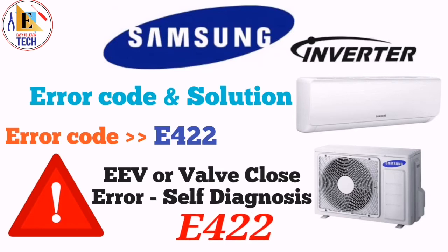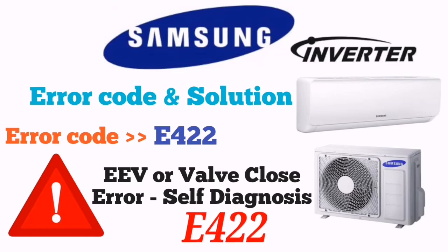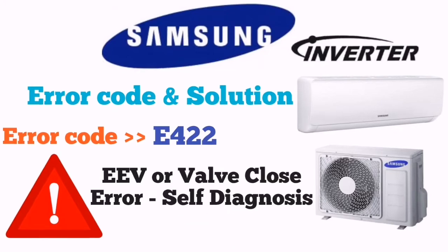If the pressure of the refrigerant is not normal, it means there is a leakage and you are getting this error due to the refrigerant leakage. And if the refrigerant is also okay, then change the outdoor PCB and start again. If your system works, it means the fault was in the outdoor PCB. If it's still not starting, then change the indoor PCB and your unit will be in working condition.